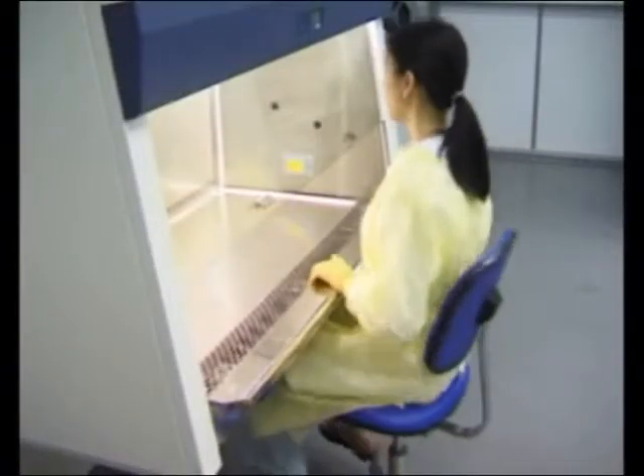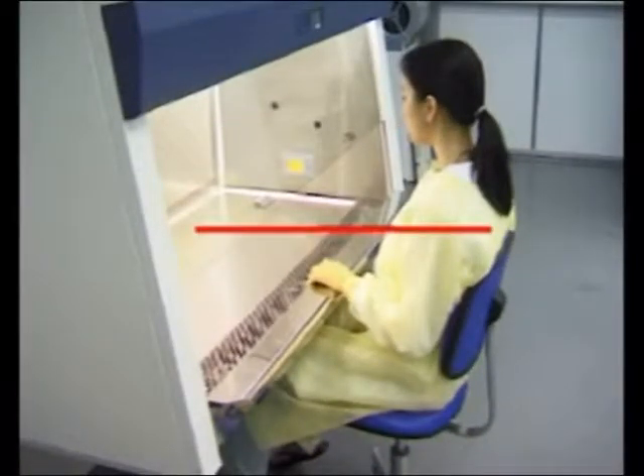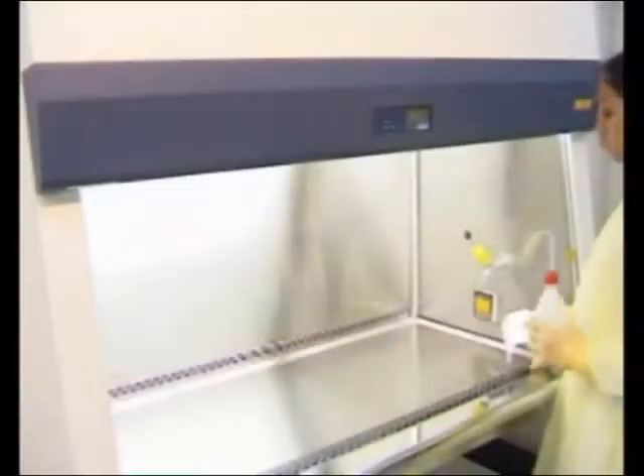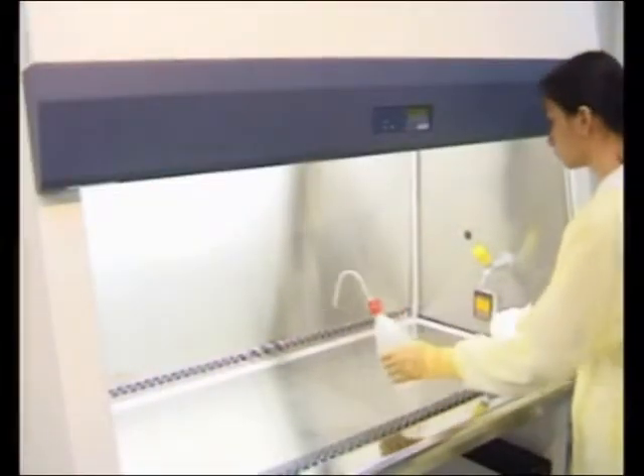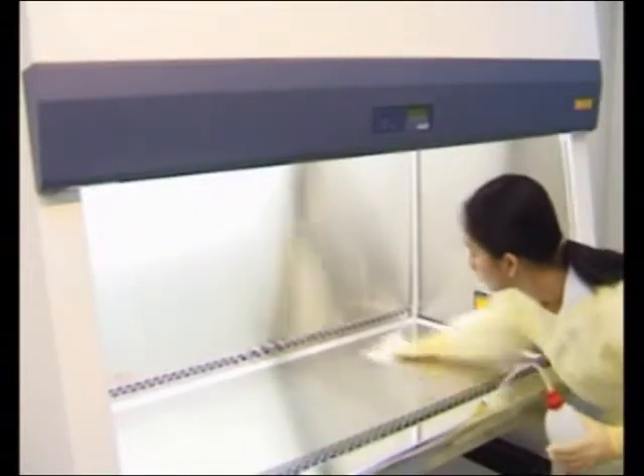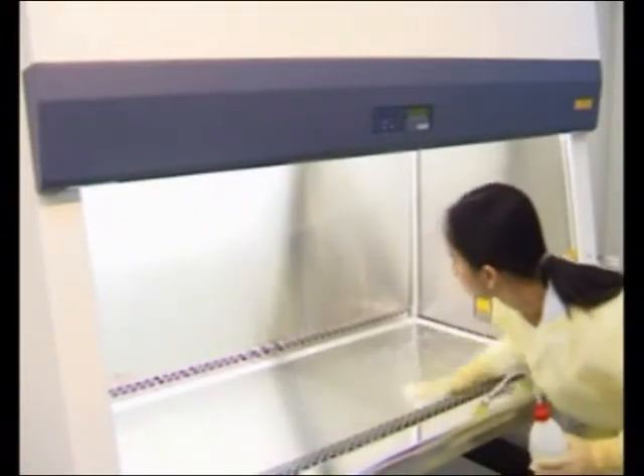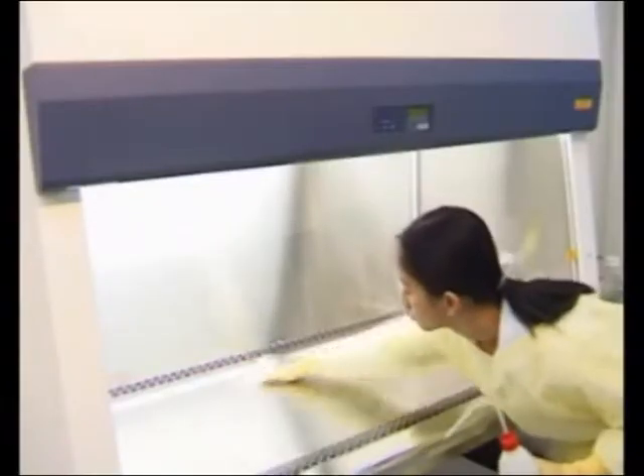Adjust the height of your lab chair so that your armpits are approximately level with the bottom of the front sliding sash. This will ensure that your face is protected by the front sash while giving you plenty of room to work. Wipe down the interior work zone surfaces with an appropriate disinfectant, including the front air grill, with a suitable disinfectant such as 70% isopropyl alcohol. The most effective disinfectant will depend on the organisms manipulated and the work conducted in the biosafety cabinet.